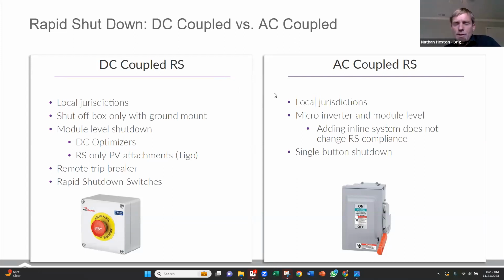For AC coupled systems, as soon as that microinverter or that string inverter loses sight of a signal coming from the grid, those modules are made to shut down. So the microinverters will shut down as soon as they don't see a signal anymore. And so you just need a disconnect on those. Typically, those are fused disconnects. So there's a fuse inside that disconnect that you see there.